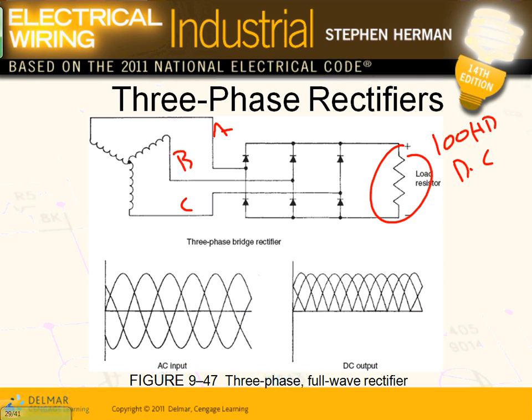Chris, we came up with a voltage of 432 volt, assuming it's right. So I converted and I'm running 100 horsepower at 432 or whatever the voltage is. I don't know if you guys can see it. This is, believe it or not, kind of an AC, with little ripples here. Here's where the DC is. Everybody can see that DC at the top here?